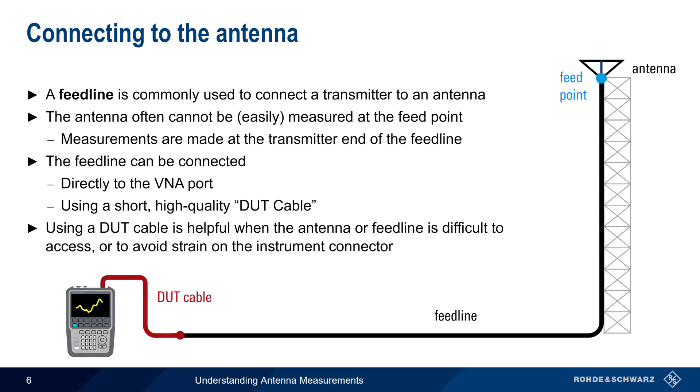Measurement accuracy is unaffected by the DUT cable, as long as calibration takes this cable into account. We'll talk more about this in detail in just a couple of minutes.